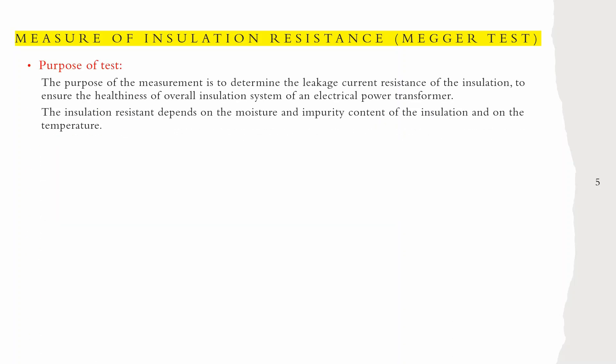Next is the measure of insulation resistance, the megger test. The purpose of this measurement is to determine the leakage current resistance of the insulation to ensure the healthiness of the overall insulation system of an electrical power transformer. The insulation resistance depends on the moisture content, impurity content of the insulation, and the temperature.